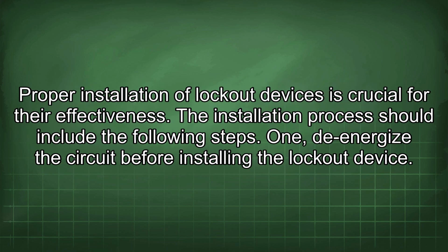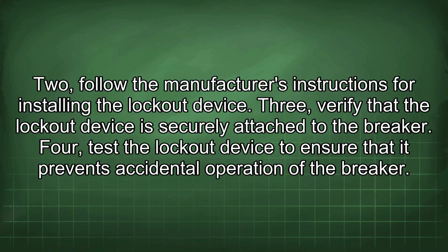Proper installation of lockout devices is crucial for their effectiveness. The installation process should include the following steps. 1. De-energize the circuit before installing the lockout device. 2. Follow the manufacturer's instructions for installing the lockout device. 3. Verify that the lockout device is securely attached to the breaker. 4. Test the lockout device to ensure that it prevents accidental operation of the breaker.